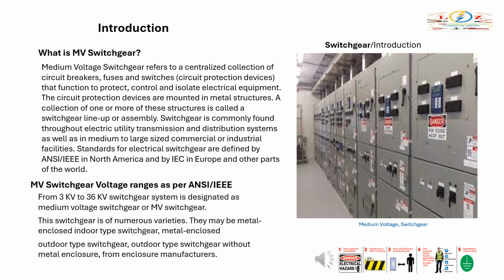Standards for electrical switchgear are defined by ANSI IEEE in North America and by IEC in Europe and other parts of the world. MV switchgear voltage ranges as per ANSI IEEE: from 3 kV to 36 kV, a switchgear system is designated as medium voltage switchgear or MV switchgear. This switchgear is of numerous varieties. They may be metal-enclosed indoor-type switchgear, metal-enclosed outdoor-type switchgear, or outdoor-type switchgear without metal enclosure, from enclosure manufacturers.